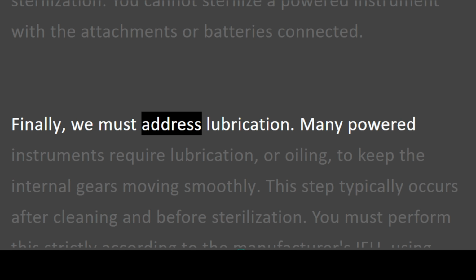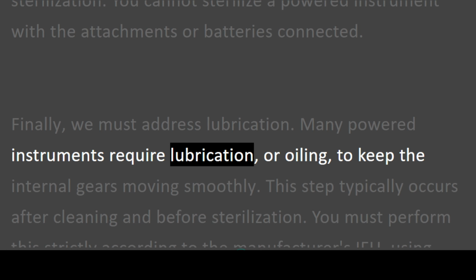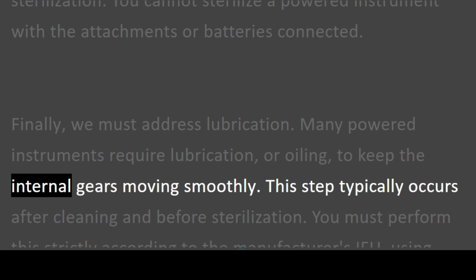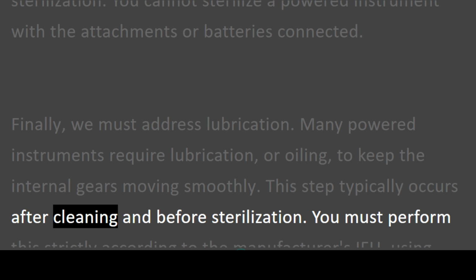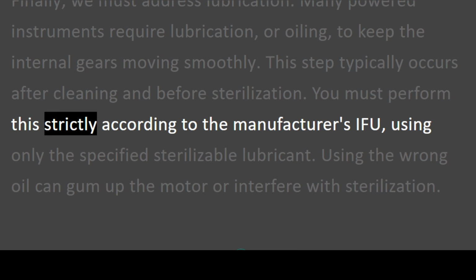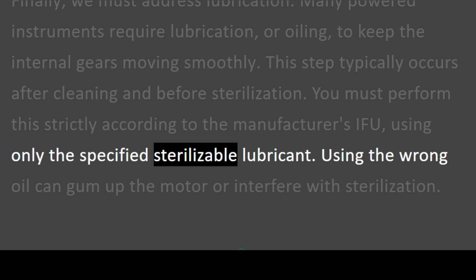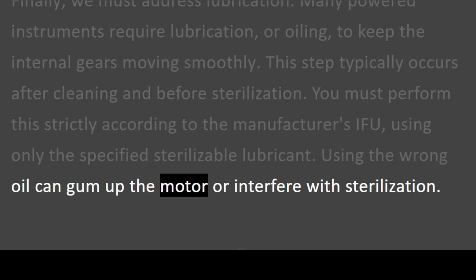Finally, we must address lubrication. Many powered instruments require lubrication, or oiling, to keep the internal gears moving smoothly. This step typically occurs after cleaning and before sterilization. You must perform this strictly according to the manufacturer's IFU, using only the specified sterilizable lubricant. Using the wrong oil can gum up the motor or interfere with sterilization.